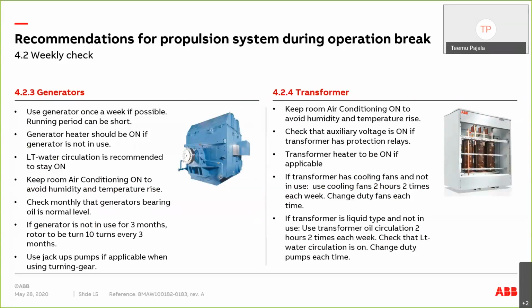Normal air conditioning and ventilation in the engine room, like in normal operation. The bearing oil level needs to be checked to make sure it's at a normal level. And if the generator has not been used for 3 months, then the rotor should be turned at least 10 times every 3 months. And remember, when rotating the shaft at slow speed, use the jack-up pumps if there are any in the generator.